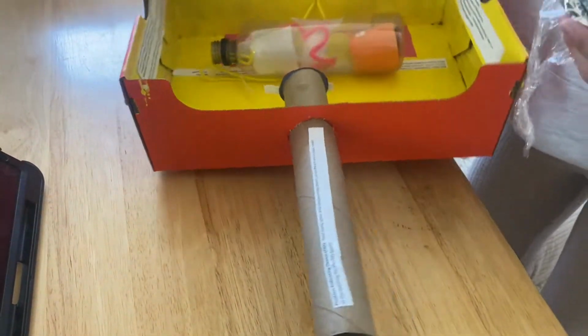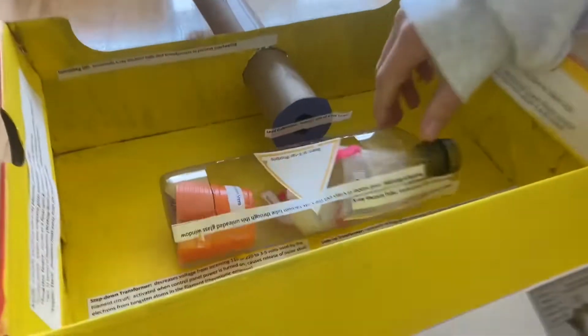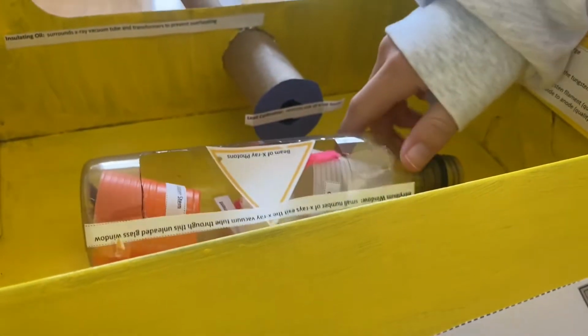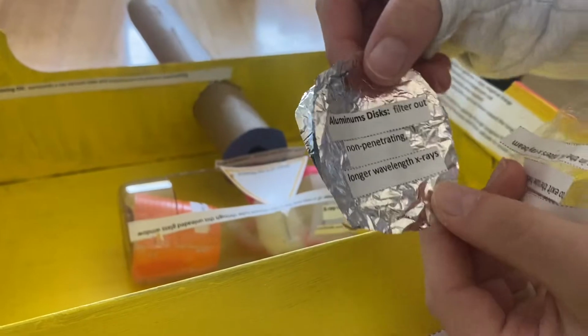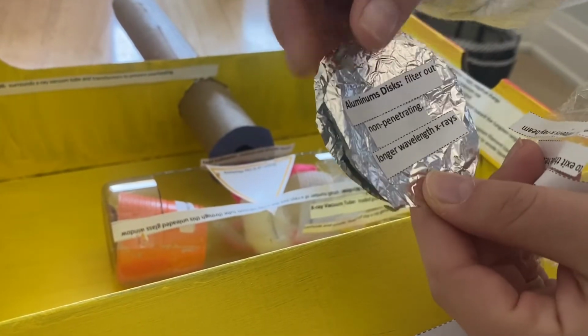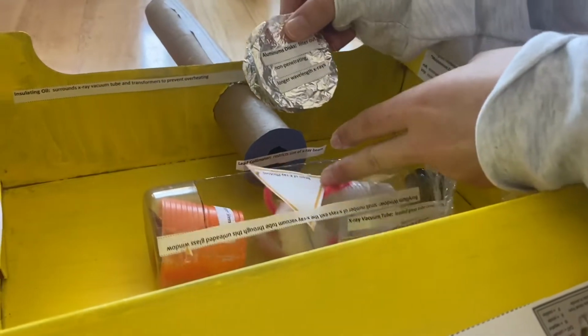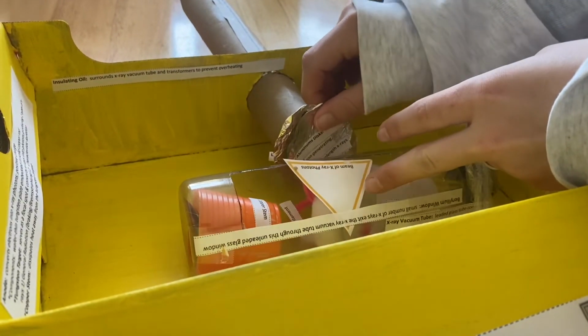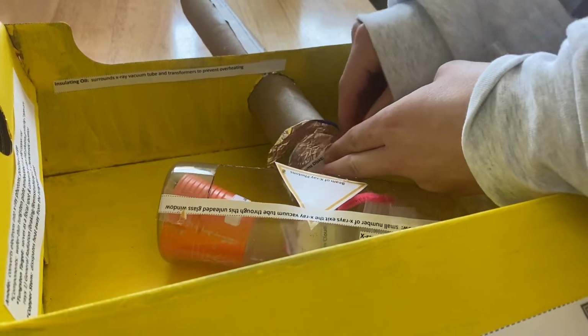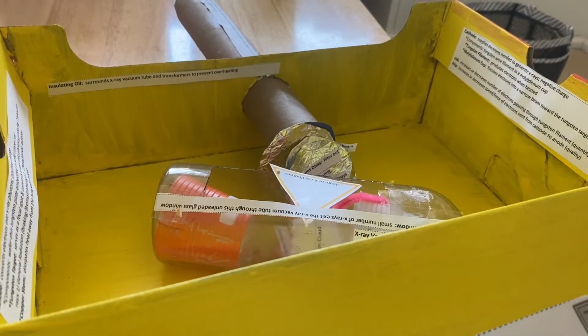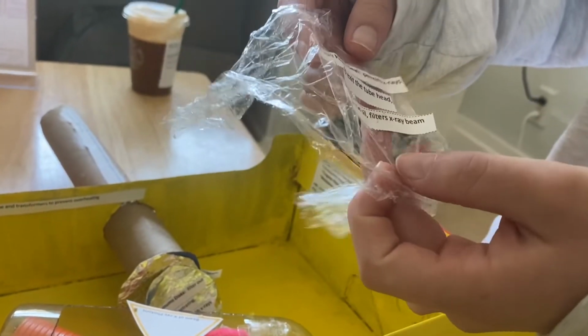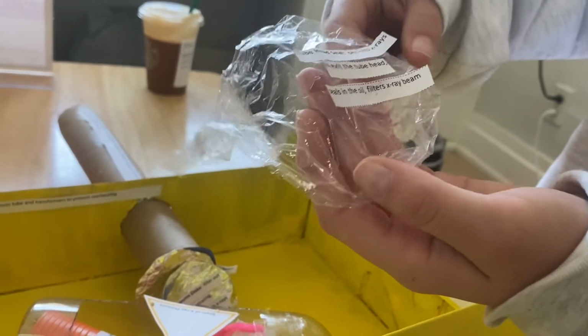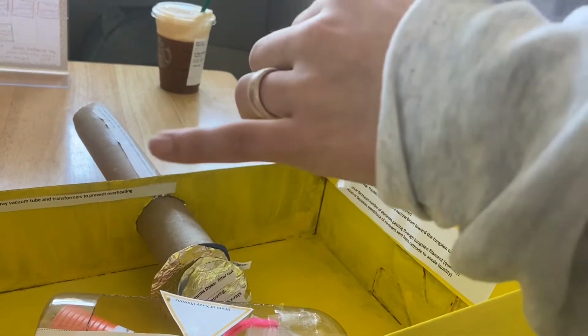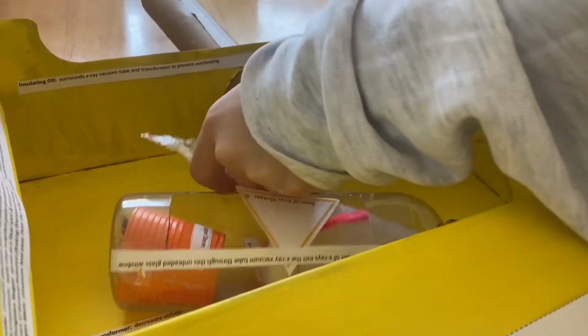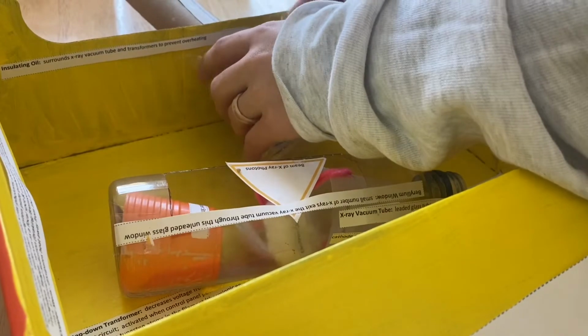Let's go to the base over here. Here we have the lead collimator, which restricts the size of the X-ray beam. And over that, we would put these aluminum discs, which filter out the non-penetrating longer wavelength X-rays. So we put those there. And then covering those, we have a seal, the tube head seal, which will permit X-rays to exit the tube head, and it will seal in the oil and filters the X-ray beam. So that will actually come up here and cover that, seal it.